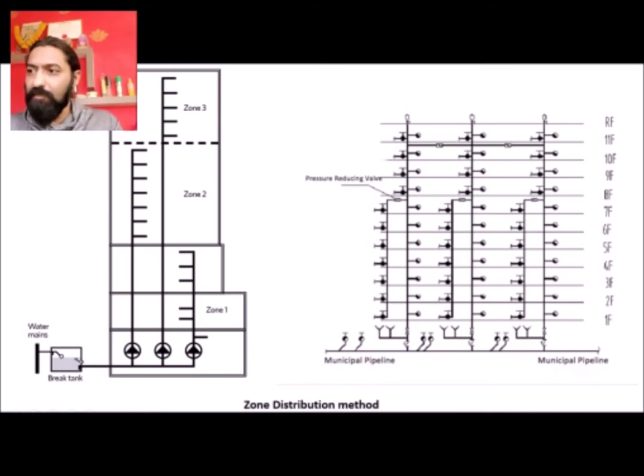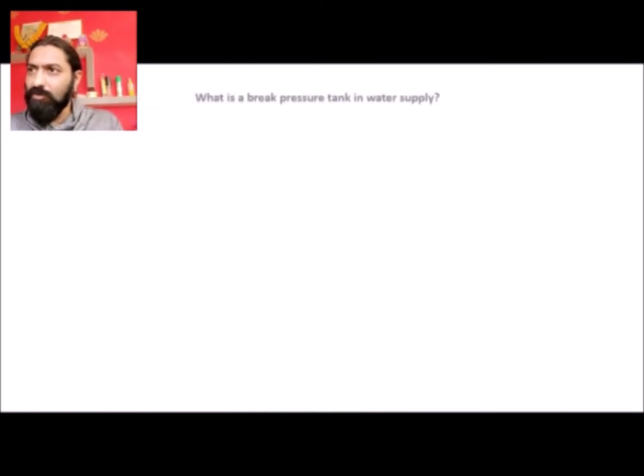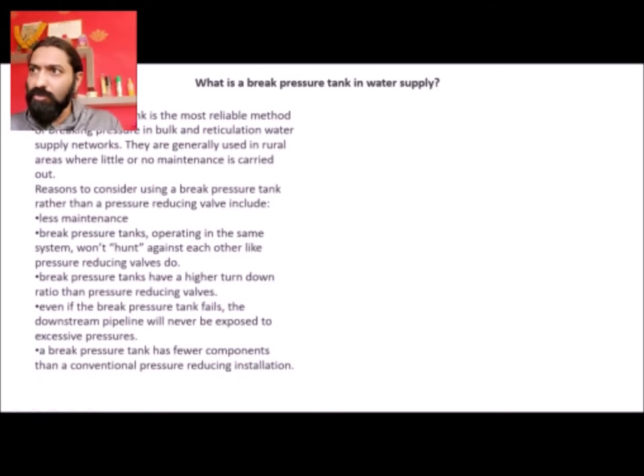In the zoning method diagram, water is fetched from the water mains, then goes to a break tank or underground tank (UGT). The building is divided into three zones — one pump and one tank for each zone. There can be individual water storage tanks, or supply can be through pressure. In the second diagram, you can see pressure reducing valves placed after certain floors, but this method is not economically ideal and requires a lot of maintenance.